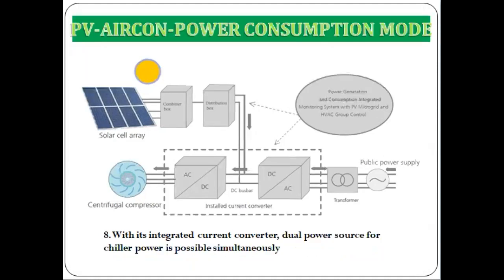Number 8, with its integrated current converter, dual power source for the chiller is possible simultaneously. In this GREE PV chiller unit, it needs to draw power from the power line in addition to the power supplied from the PV system. The integrated monitoring system displays the PV aircon power consumption mode when power generated by the PV system is less than the power consumed by the air conditioning equipment. This condition can be observed when the load profile of the GREE PV chiller is at peak, but the weather condition is fair.